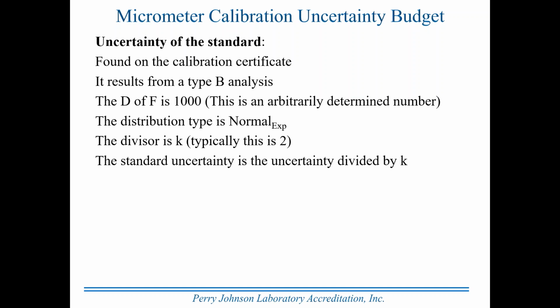Standard uncertainty is the uncertainty divided by K. So if we're told what the uncertainty of the standard is, and we're told what the coverage factor is, we divide the uncertainty by K, and we get the standard uncertainty, or standard deviation, of the uncertainty distribution.